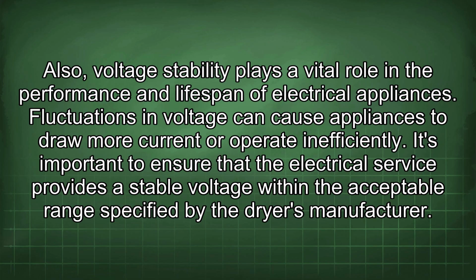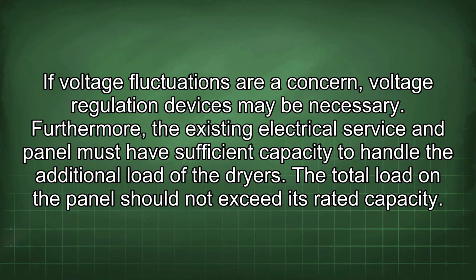Also, voltage stability plays a vital role in the performance and lifespan of electrical appliances. Fluctuations in voltage can cause appliances to draw more current or operate inefficiently. It's important to ensure that the electrical service provides a stable voltage within the acceptable range specified by the dryer's manufacturer. If voltage fluctuations are a concern, voltage regulation devices may be necessary.